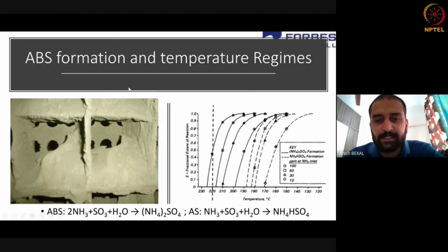So you need to design the system so this doesn't happen. This graph, which you can look at later, shows temperature versus the fraction of ammonium bisulfate forming for a given amount of ammonia. For example, take the curve marked with a circle, which is 100 ppm: if you have 100 ppm of ammonia at 220 degrees centigrade, you'll get about 45 ppm of ammonium bisulfate forming.